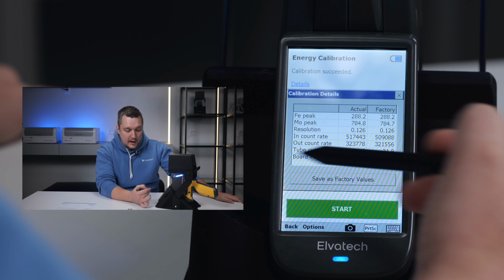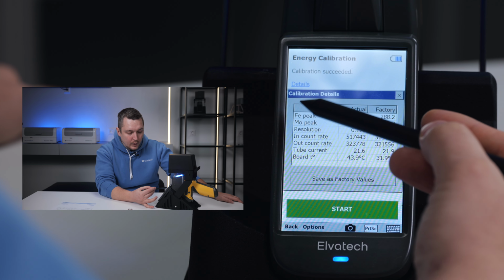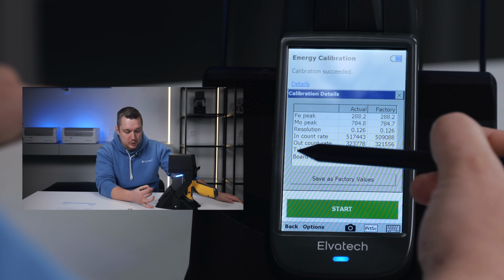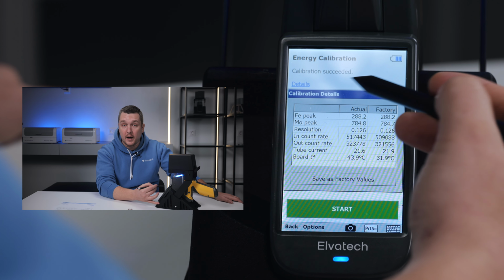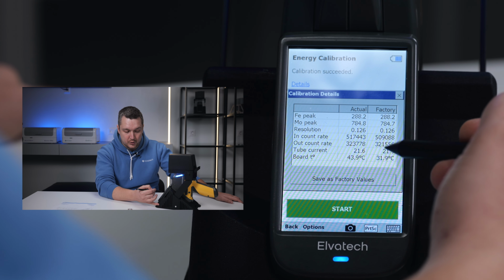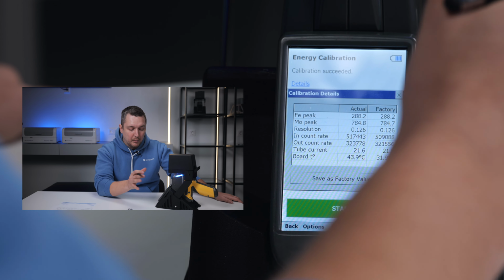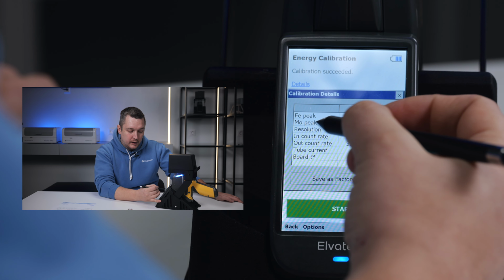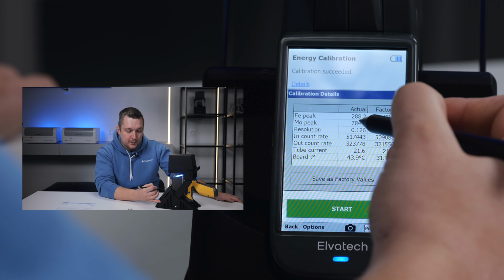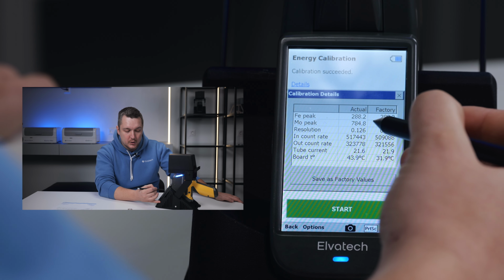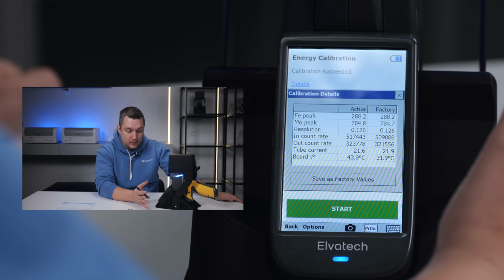We're interested in details. So just click on the details once, and you see the table on the screen. Here we have 3 columns. The first column has ferrum peak, molybdenum peak, resolution, and so on. The second column is the actual values that we have just measured. And the third column is the factory values. So, first of all, we need to compare the resolution of the detector. This value should be no more than 0.140. So the less this value, the better it is. So here we have 0.126, and the factory value was 0.126 also. So we don't need to worry, everything is fine with our analyzer.